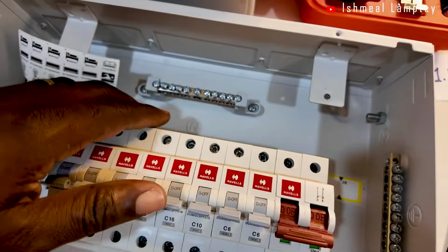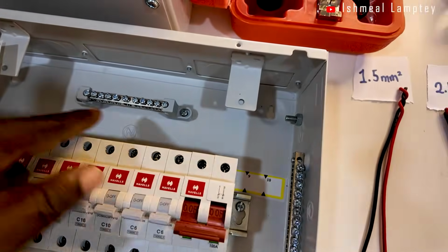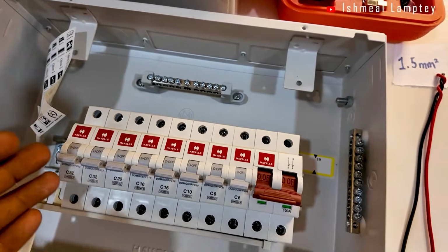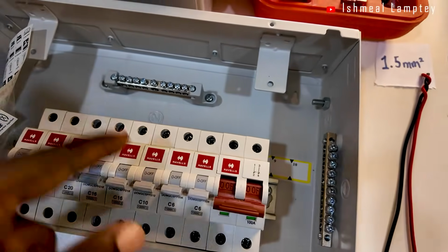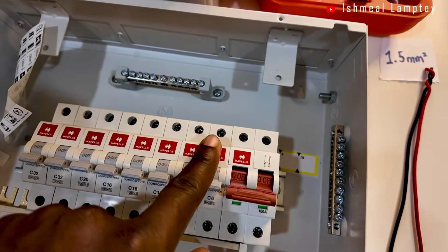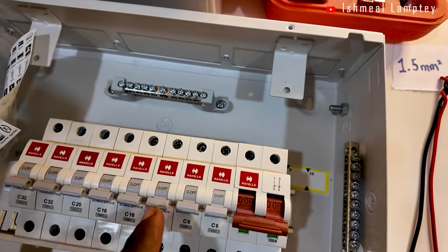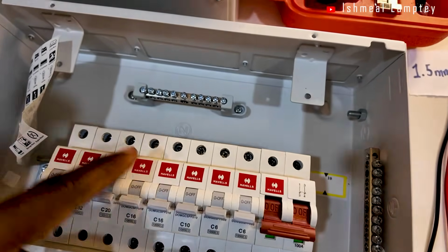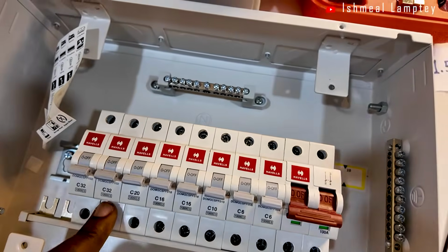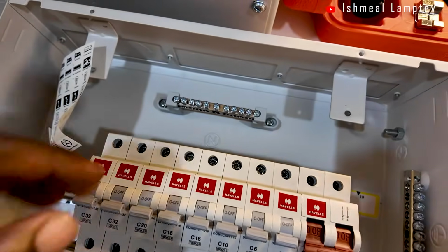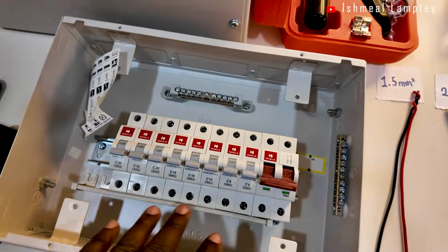Then you have these smaller cable sizes that go to each breaker, depending on the size you're working with. For 6 amps, you have a 1.5 mm cable. For 10 amps, maybe also 1.5. For 16 amps, you have 2.5. For 32 amps, or 20 amps and 32 amps, we can use 4 mm.